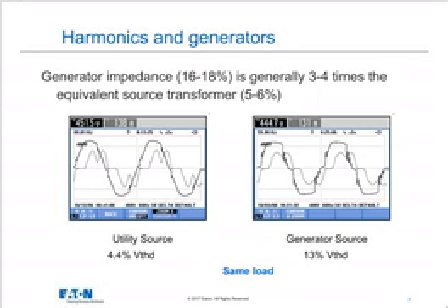Now with generators, this is actually an example of 4 variable frequency drives running in my experience center where we run here in Pittsburgh. I basically have the same load on the utility source and then switch over to the generator source, and you can see the significant voltage distortion. So it goes from about 4.4% to 13%. Again, the reason is that the impedance of the generator is about 3 times as much. So it follows, just with Ohm's law, that voltage distortion equals current distortion times harmonic impedance. So the harmonic impedance is 3 times as much. The voltage distortion is 3 times as much.